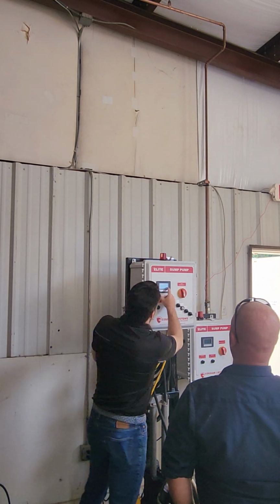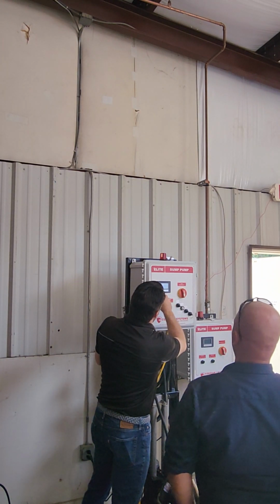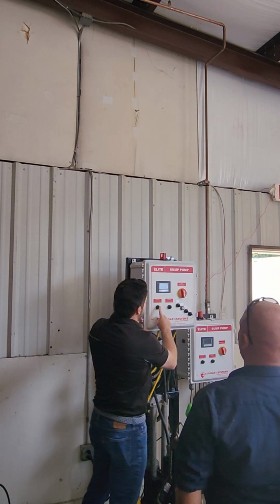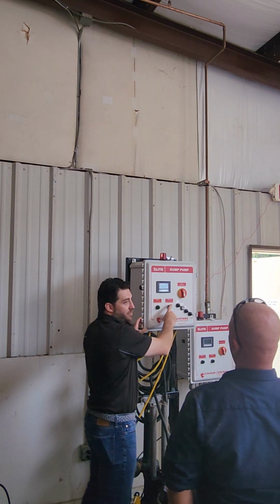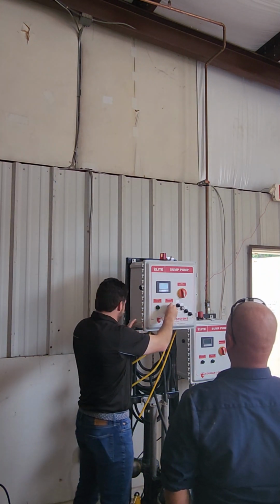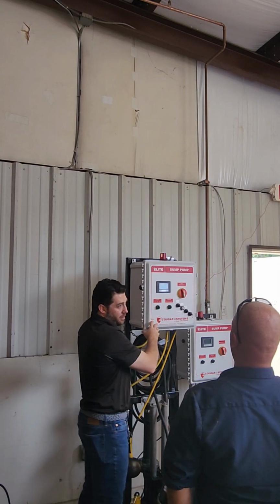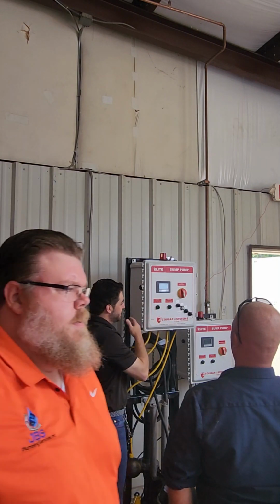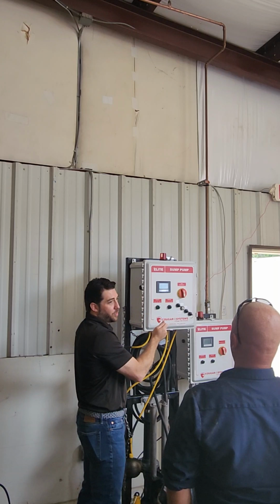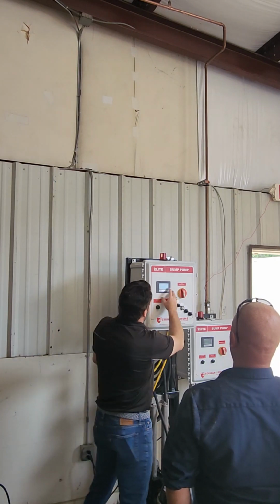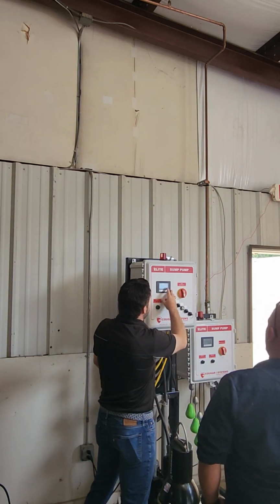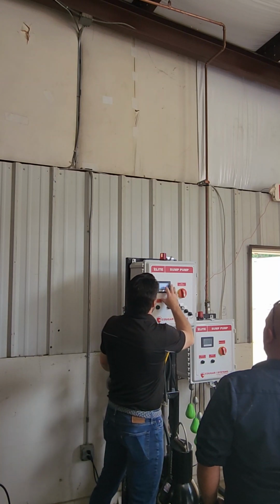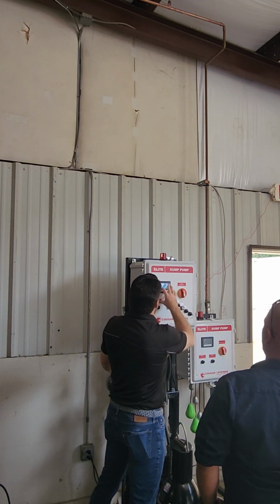So if you go from the home screen, you click on the test button right there, and you want to put the pumps into off when we do this, because the way that we build the high-level alarm on this panel is it bypasses the PLC, goes straight to a relay, and pulls in both the motor contactors. So it's still going to do that in this test screen. So real quick, I'm going to put this back to 4 floats so it makes a little more sense.